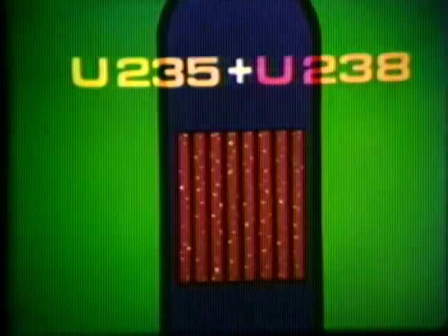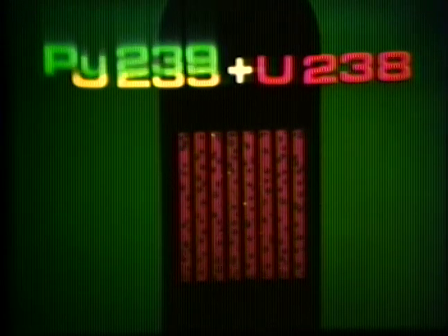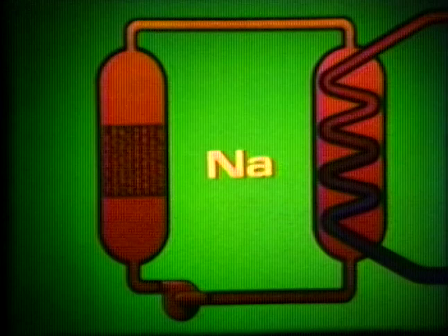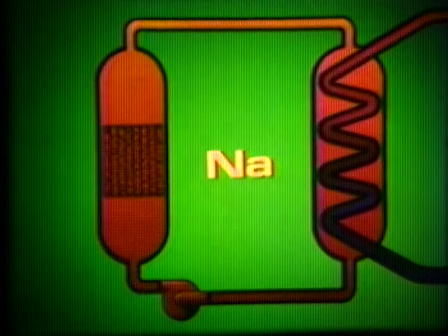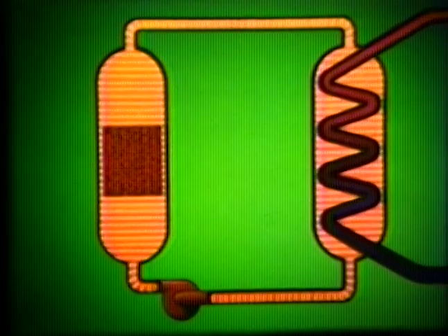First, the normal fissile isotope, uranium-235, is replaced by plutonium-239. In addition, since the breeding concept requires a chain reaction employing fast neutrons, a coolant had to be selected which does not slow down neutrons, sodium. This metal, which is liquid above 100 degrees centigrade and does not have to be pressurized, is an exceptional heat conductor.